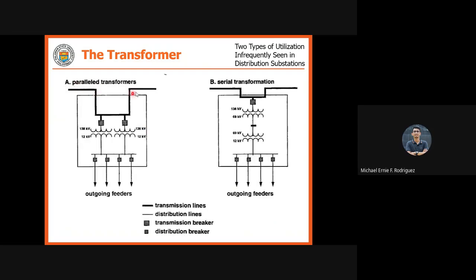First, we have parallel transformers. These are infrequently seen, not commonly found on a system. This is a parallel transformer: you have two transformers in parallel, then a common bus, going to your feeders. This is not how our Paleco substation looks. Although the Paleco substation has two transformers, the bus of transformer 1 is a different bus, and there is another bus for transformer 2, with only a tiebreaker connected. It is not a single bus like this one. They are separate, connected by a tiebreaker only.